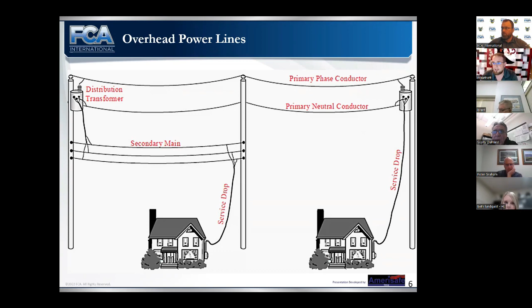Our next question is, are these lines insulated? Only by distance. Your secondary main is not going to be insulated. Your primary and neutral conductors up top are not going to be insulated - they weigh too much to insulate and hang in the air. So the way that we insulate power lines is by distance. The problem is that as painters, as finishers, we often bring mobile elevated work platforms, roller poles, extension ladders, and other things that can get us closer to those power lines than we would be on the ground. So we need to take that into consideration. The service drop is sometimes insulated, but you cannot tell just by looking at it. Sometimes the service drop that goes between the building and the pole only has weatherproofing on it to extend the life of that line.